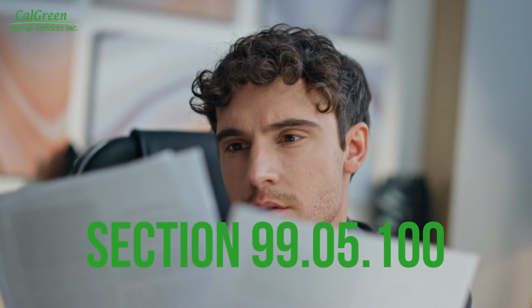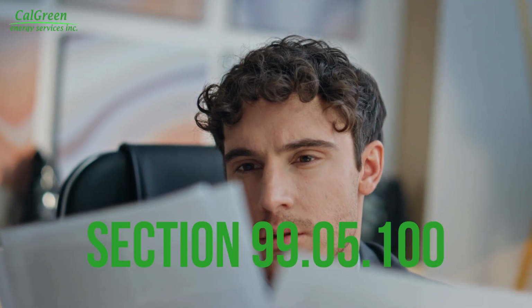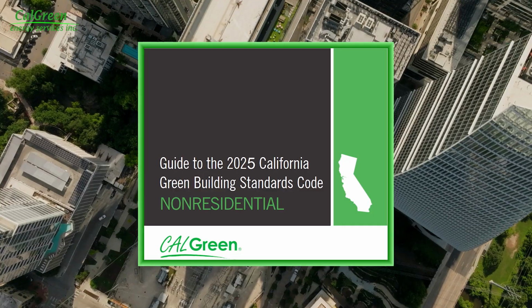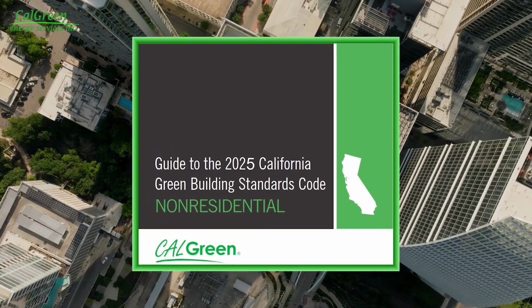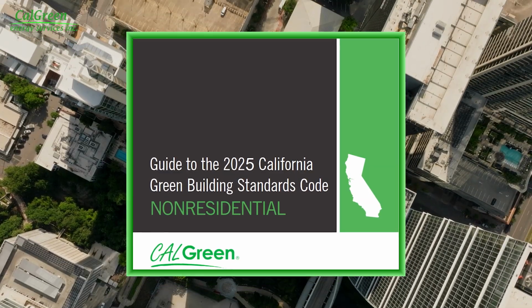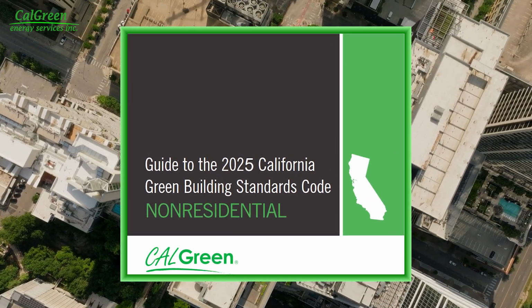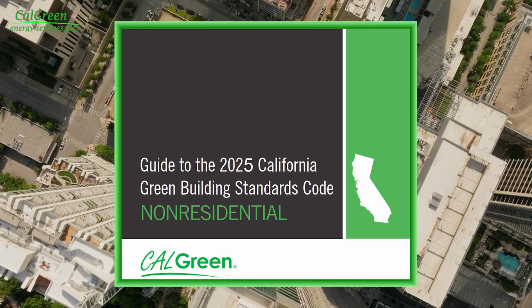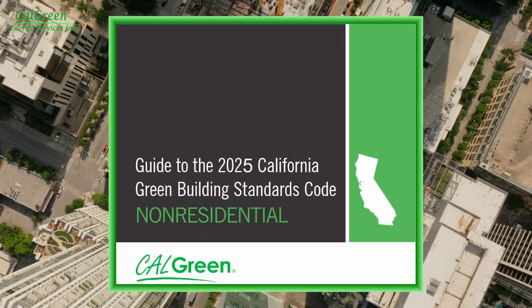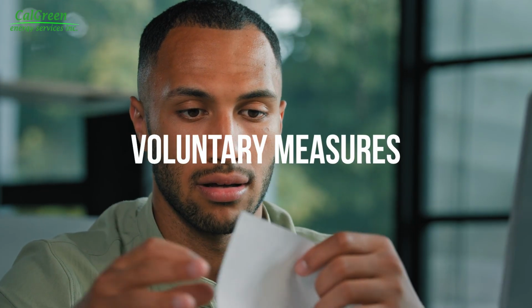To find the commissioning requirements, look at Section 99.05.100 of the Los Angeles Municipal Code. This section adopts the current California Green Building Standards Code, known as CalGreen, specifically Chapter 5 of the Non-Residential Mandatory Measures. It's important to note that the voluntary measures of CalGreen have not been adopted by the city, meaning compliance with those is not required.